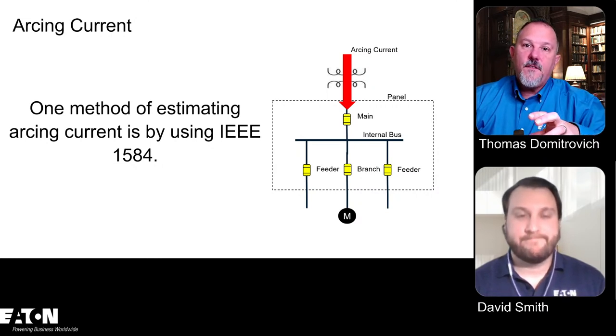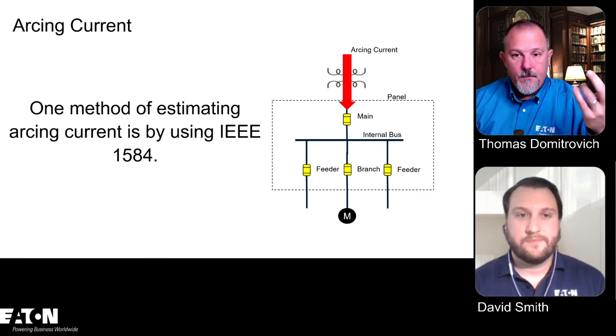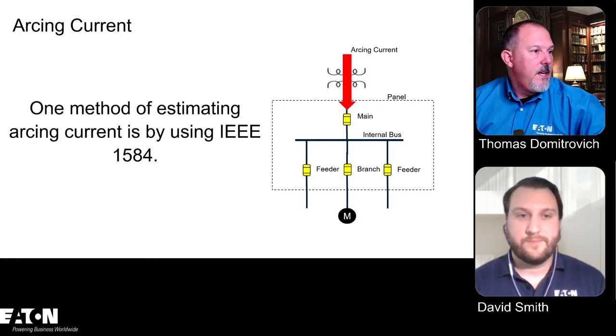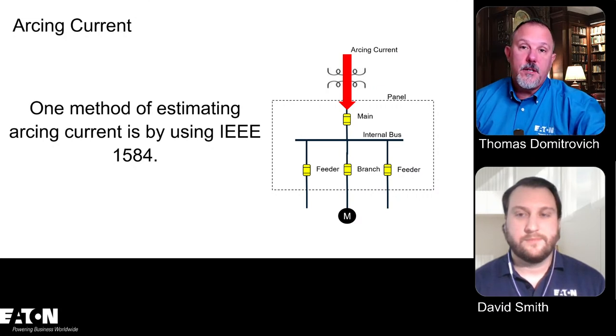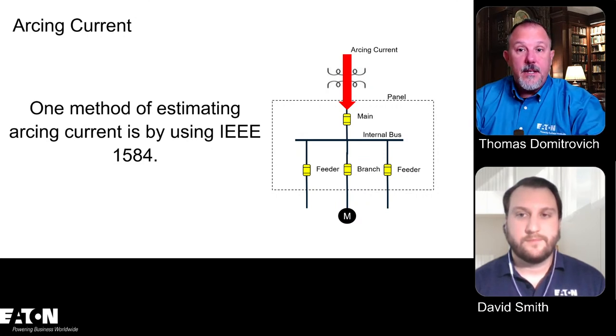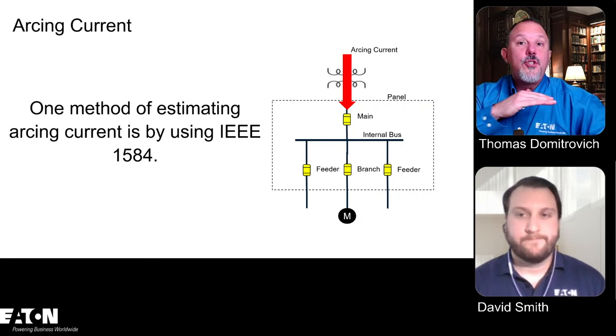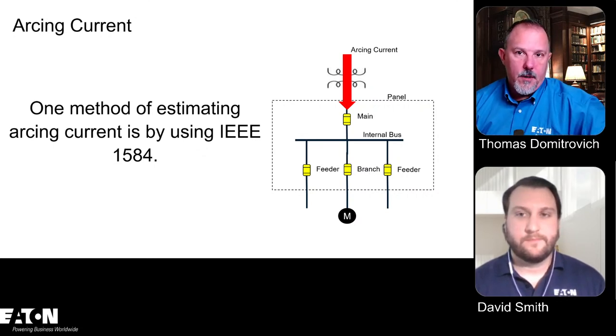So if I go down to 800 amps, and we're definitely bouncing around here, let's look at the language on when this applies. If I go to 800 amps, I look at my options. My options are basically, if my arcing current is in the instantaneous region, I don't need an arc energy reduction method, because the instantaneous is the arc energy reduction. So I would not have to do anything for an 800 amp breaker.